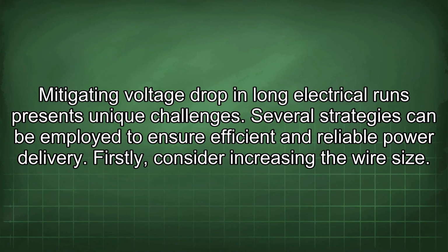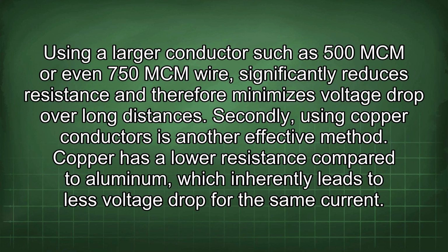Mitigating voltage drop in long electrical runs presents unique challenges. Several strategies can be employed to ensure efficient and reliable power delivery. Firstly, consider increasing the wire size. Using a larger conductor such as 500 mcm or even 750 mcm wire significantly reduces resistance and therefore minimizes voltage drop over long distances. Secondly, using copper conductors is another effective method. Copper has a lower resistance compared to aluminum, which inherently leads to less voltage drop for the same current.